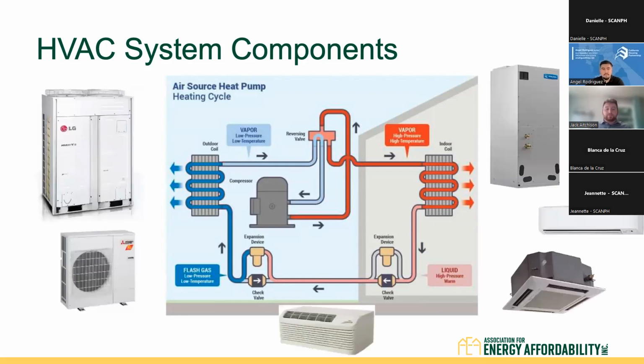Next slide. And going back to those images previously, this is what you'll see when you're looking at a heat pump and sort of the location of these units. So on the left, we have our outdoor units, our compressors. This is going to have your outdoor coil, your compressor, your reversing valve. They're all going to be sort of in this box on the outside. And then flipping over to the inside, we have our in-unit air handlers. We have our mini split head units. We have our diffusers. This is what's going to be on the inside. This is what's going to have our indoor coil and our air filters. And then on the bottom, we have a packaged terminal heat pump where all of these components are going to be within that packaged heat pump.